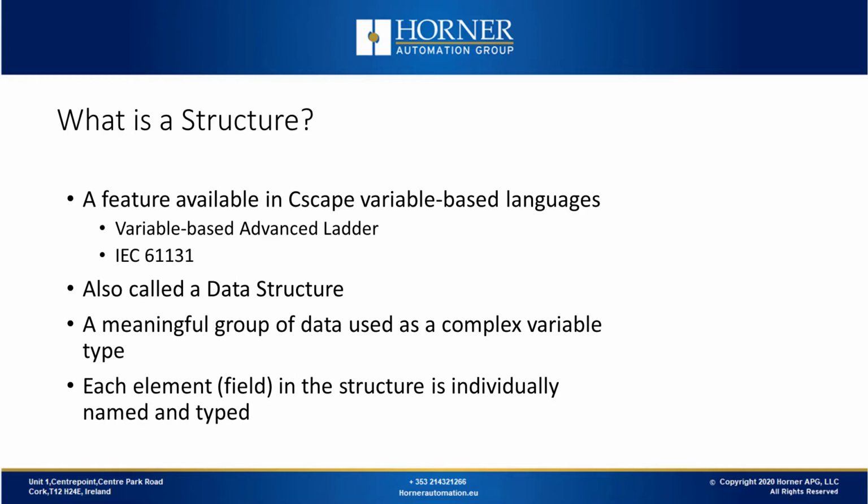So what is a structure? A structure is a feature that's available in our Cscape variable-based logic languages. It's available in variable-based advanced ladder as well as IEC 61131. Structures are also called data structures. They are a meaningful group of data that is used as a complex variable type. Each element in the structure, sometimes called a field, is individually named and typed.